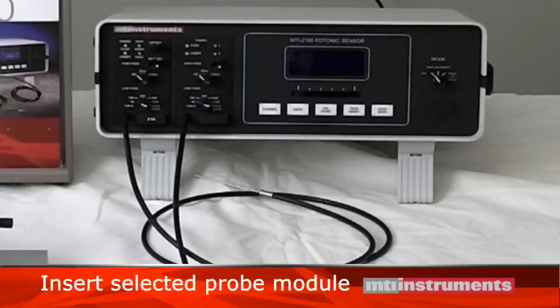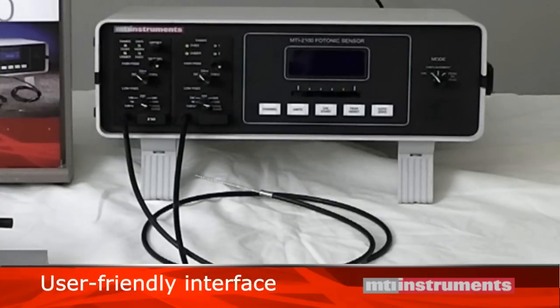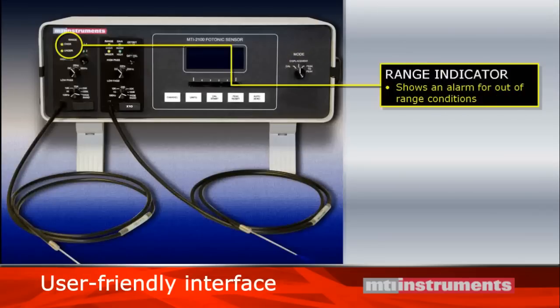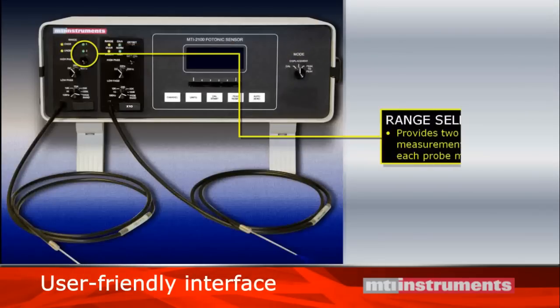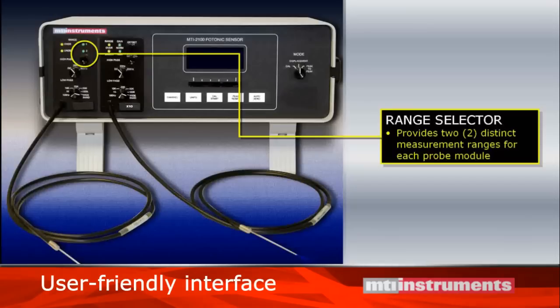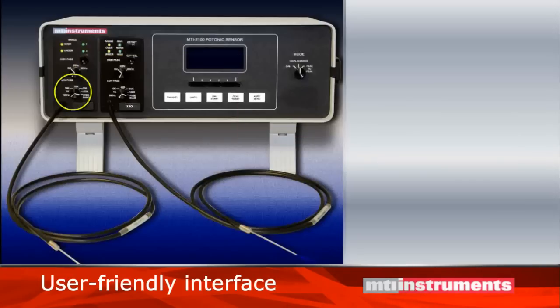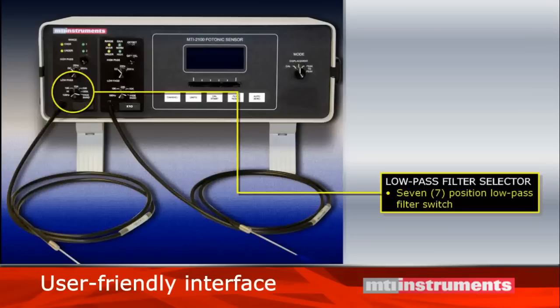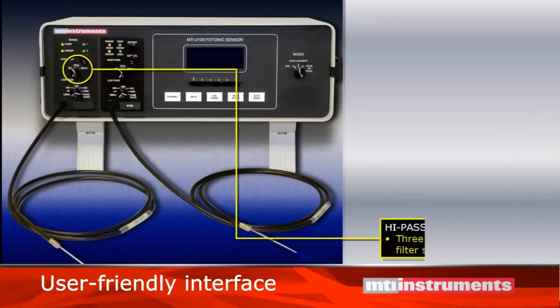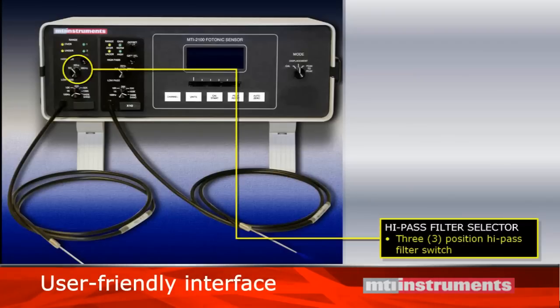Before we proceed, let me quickly run through our user-friendly interface. Range indicator shows out-of-range conditions. Range selector allows you to select operation on either the front or the back slope. It also applies the appropriate sensitivity factor to the digital display, allowing true engineering units of displacement to be provided. 7-position low-pass filter adjusts the system's response time from wideband, or the fastest response time, to the slowest bandwidth, 100 Hz. 3-position high-pass filter allows you to create a bandpass filter on the output. This helps eliminate vibration, for example, caused by building or machinery vibration.